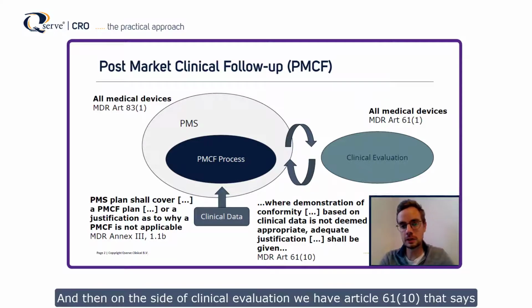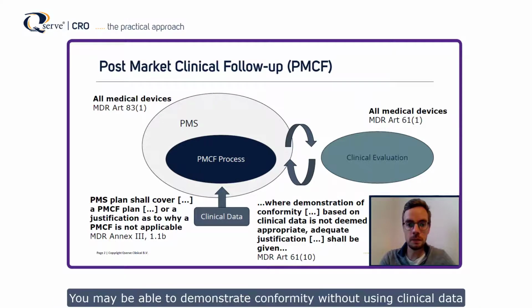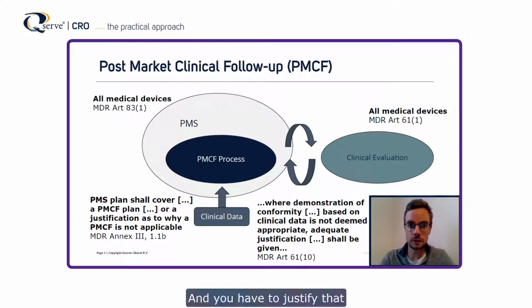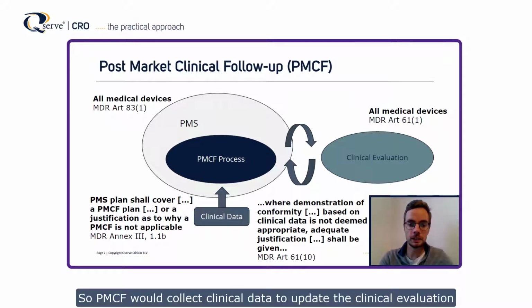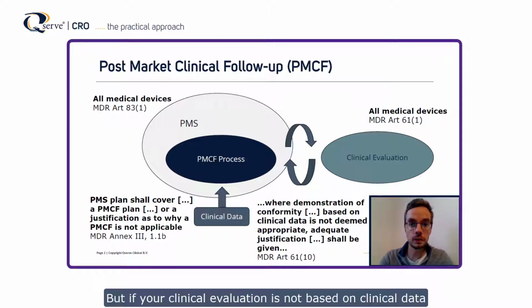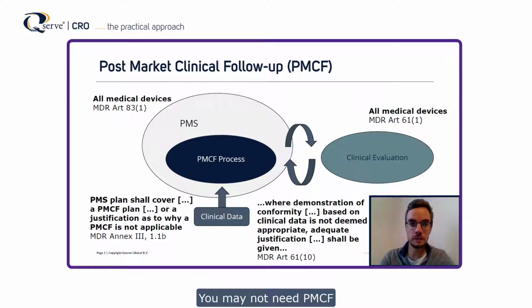And then on the side of clinical evaluation, we have Article 61(10) that says you may be able to demonstrate conformity without using clinical data. And you have to justify that. And here's the connection. So PMCF would collect clinical data to update the clinical evaluation. But if your clinical evaluation is not based on clinical data, you may not need PMCF.